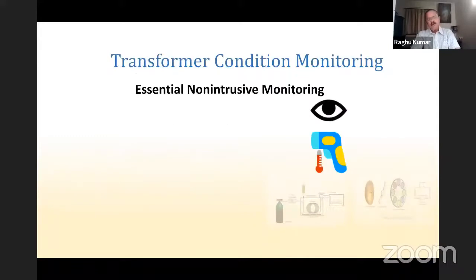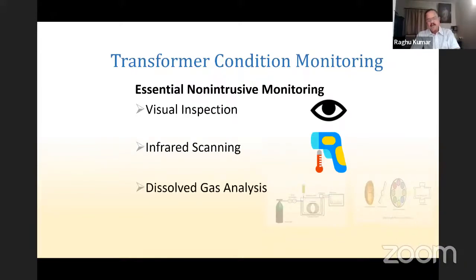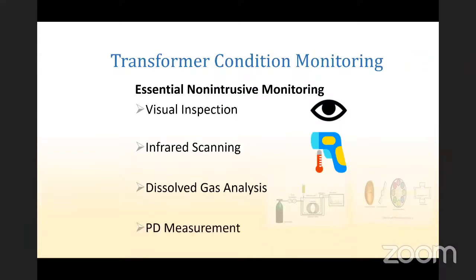What kind of monitoring can we do? Most of the monitoring is non-intrusive while the transformer is still running. The first one is a visual inspection. And the next stage, we go in for an infrared scanning. And the last stage is dissolved gas analysis. And normally, a PD measurement is carried out in certain very important transformers.